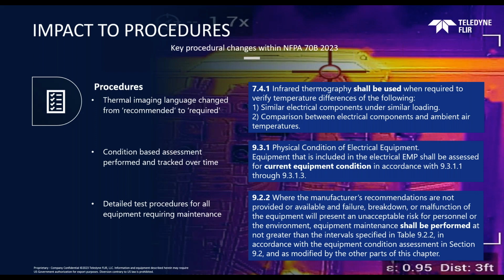From the similar electrical components perspective under similar loading, NFPA-70B requires that the load be no lower than 40%. So the load of the equipment needs to be at least 40% to be considered in the testable state, as well as any other components you're comparing against have to be under similar load.